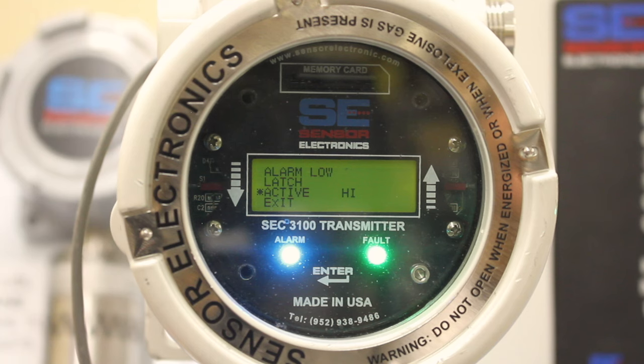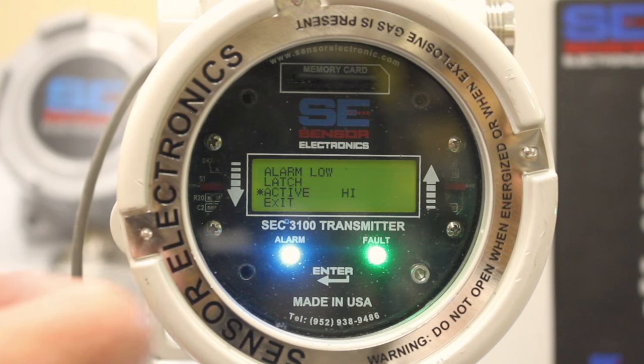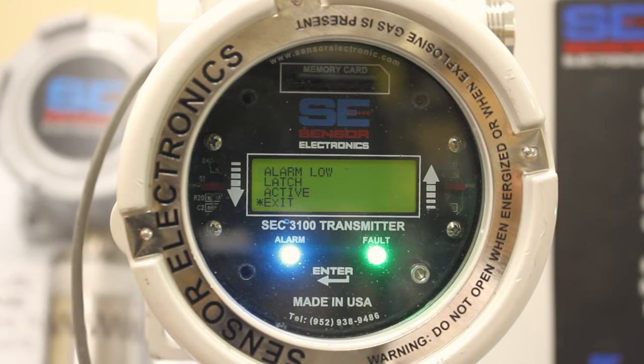And the only one that I'm familiar with that we use active low is when the transmitter is used with an oxygen sensor, because typically you're looking for oxygen deficiency, so then you trigger on a falling edge. So once the alarm level goes below that alarm, then it will actually energize. But in most cases they're programmed to be active high. And then once you have your relays all programmed, you just arrow down to Exit, select Exit, and then you would just sequence through to your next relays.